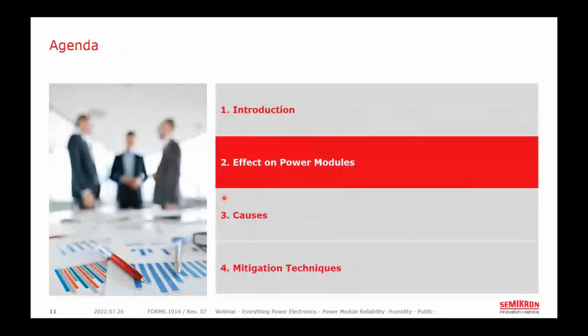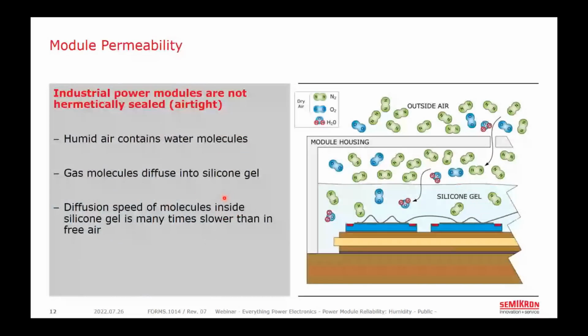The effect on power modules. So most industrial power modules in the power ranges we're discussing here, say 1200 volt or 1700 volt IGBT modules with multiple switches bigger than 10 amps, are not hermetically sealed. That means they are not gas tight, and that air and the water vapor contained within can move into the module. The air can move through seams in the plastic housing when housing is made from multiple pieces of plastic, or seams around the electrical terminals, or in the holes that were used for filling the silicone gel during module production, or even through the plastic itself.